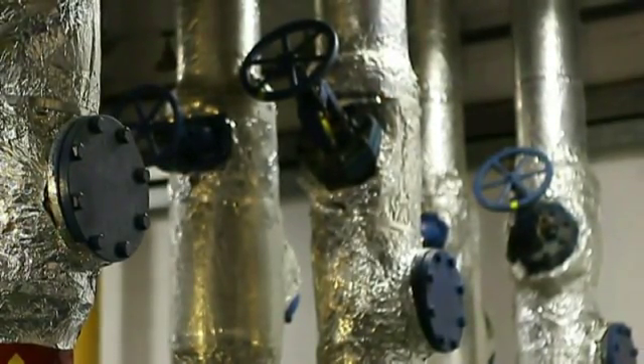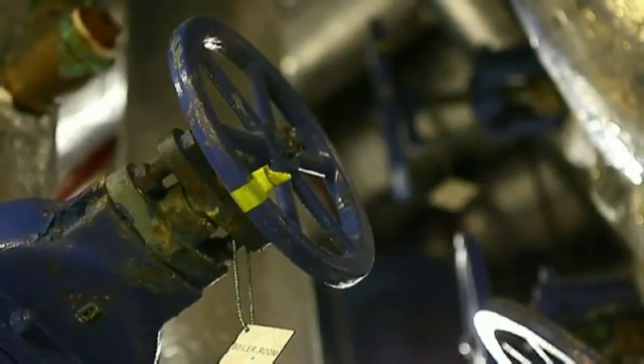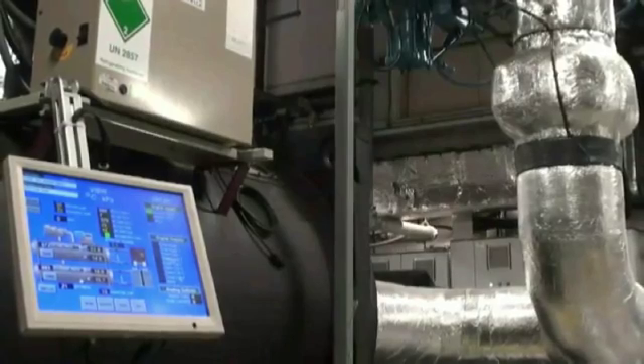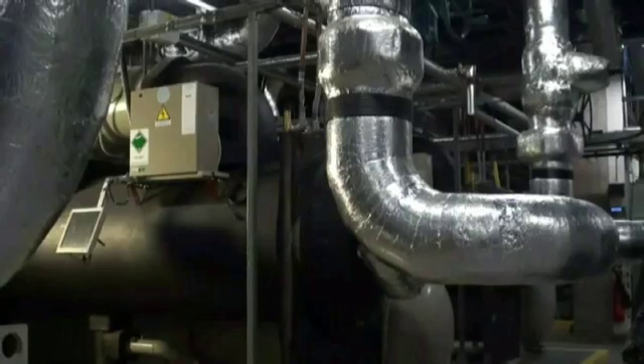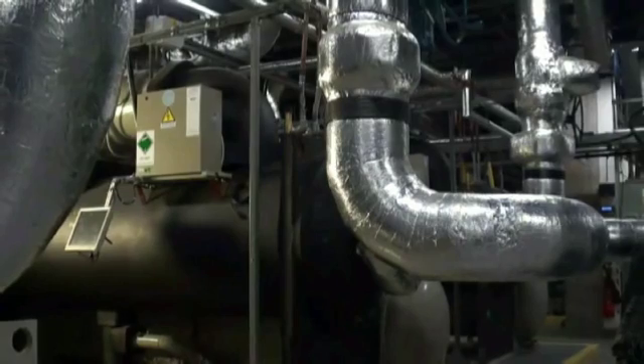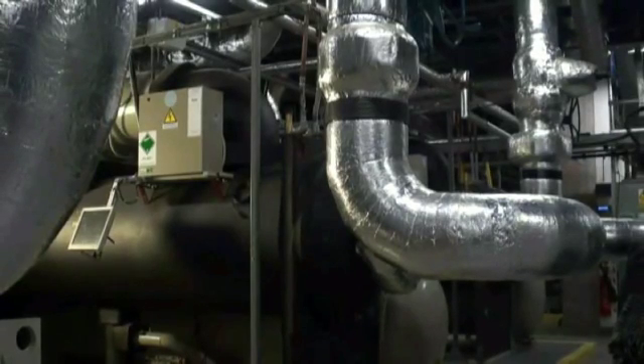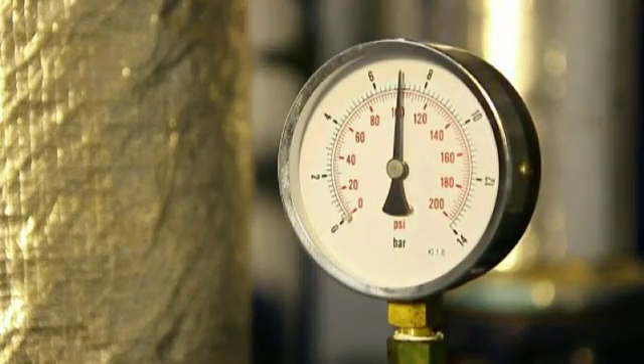We had inherent problems with our calorifiers due to the building being in a hard water area. Consequently, we looked at the Scale Watcher product. It really seemed to fit the bill, so we had that installed on our boosted water systems, and the results have been remarkable. When we opened the vessel up for inspection, we found it was completely clean, no scale build-up whatsoever. When we used to strip the calorifier out, it could take a day, 2 days, possibly even a week. Now it's stripped down and back running within a 4-hour period.